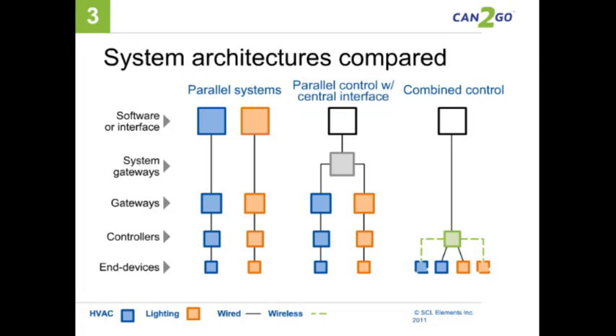Now, some manufacturers realized that this was a lot of overhead and that there really wasn't a need for two different software platforms. So they came out with parallel control but with a central interface. That's the second image here in the middle of this slide, where the end devices are separate, and the controllers and gateways are separate, but the system gateways and the actual software interface for your building management system actually combine both HVAC and lighting. That's a first good step in the right direction.